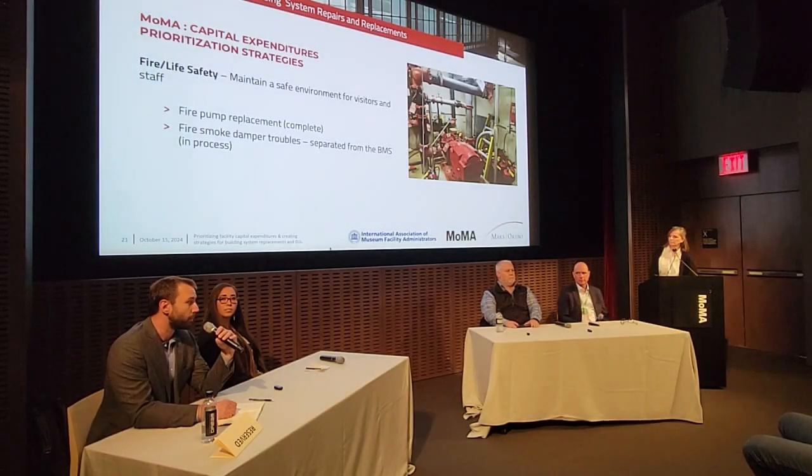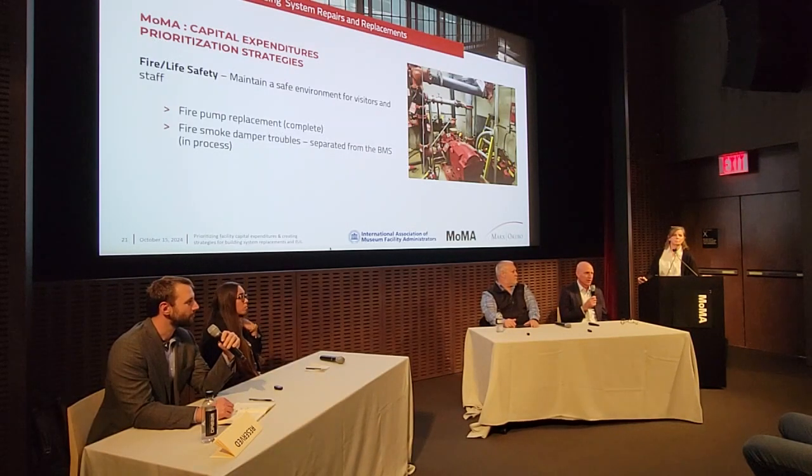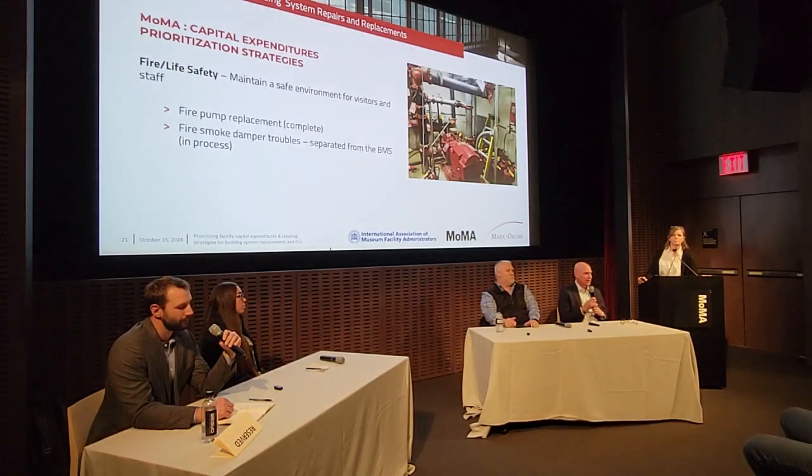So a good portion of the dampers. They've just been working over the years after that was identified to get the system back in place. And I think, according to Richard, down to like a dozen that are still an issue, that are hard to reach areas. Yes. Our main atrium exhaust system is about 250,000 CFM. So you can imagine how much air that is.